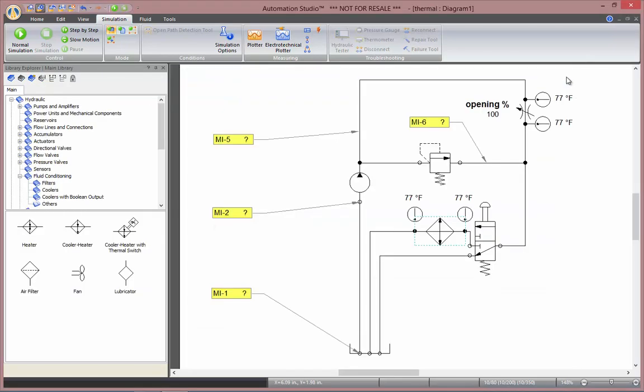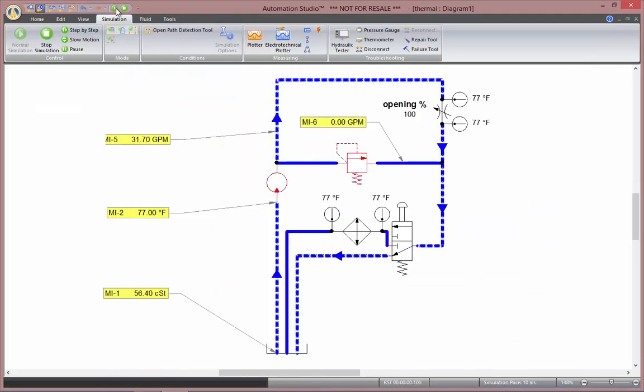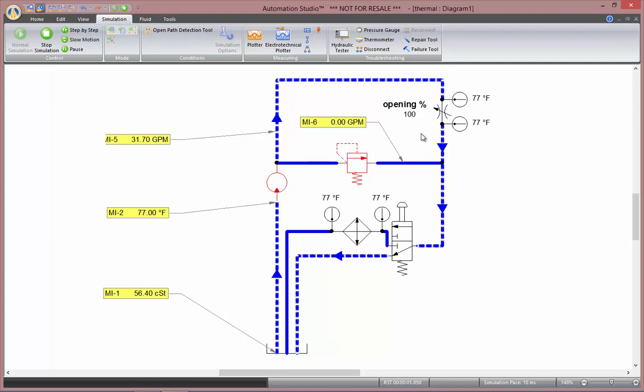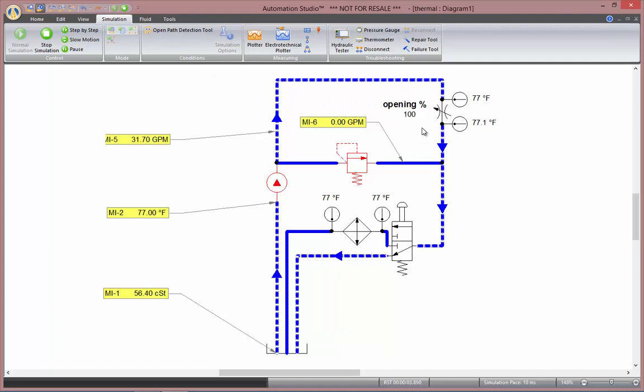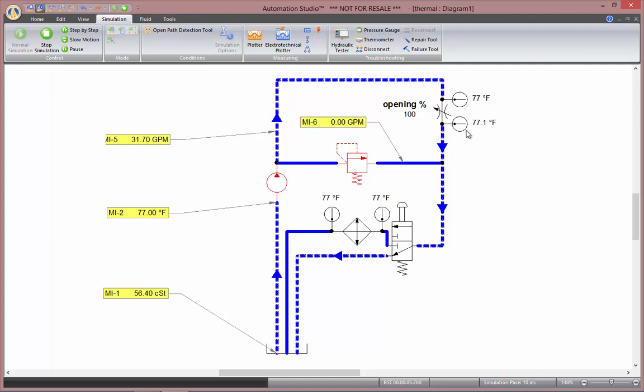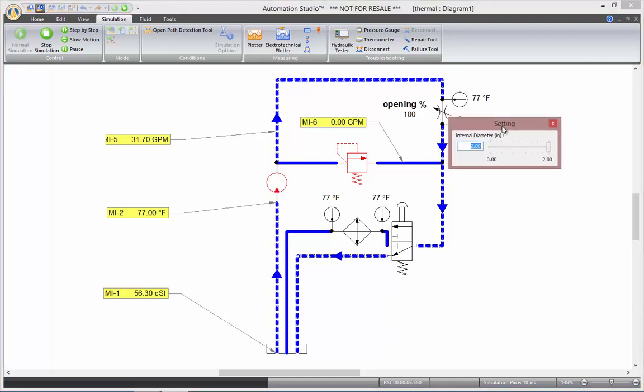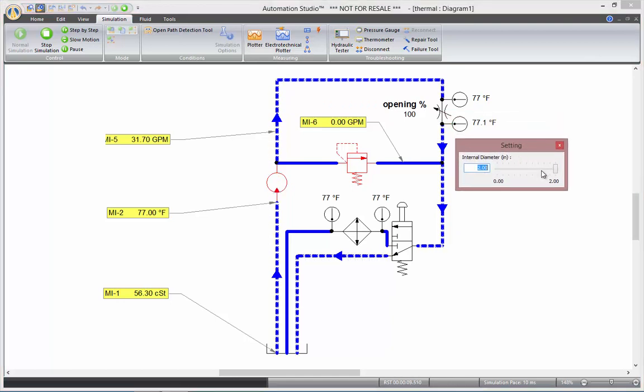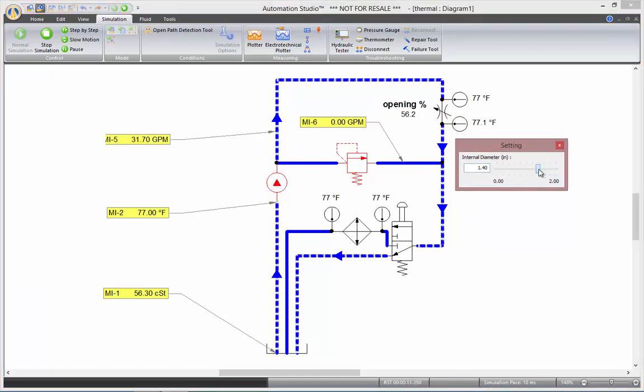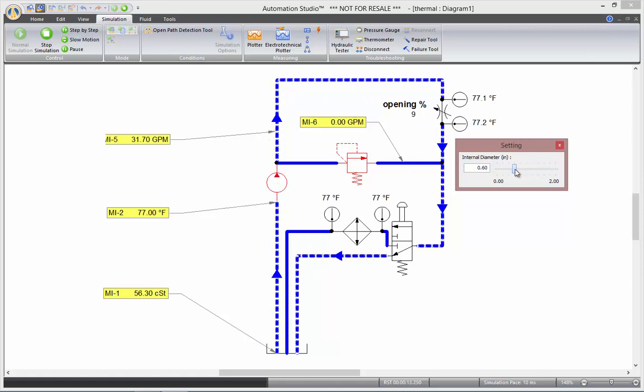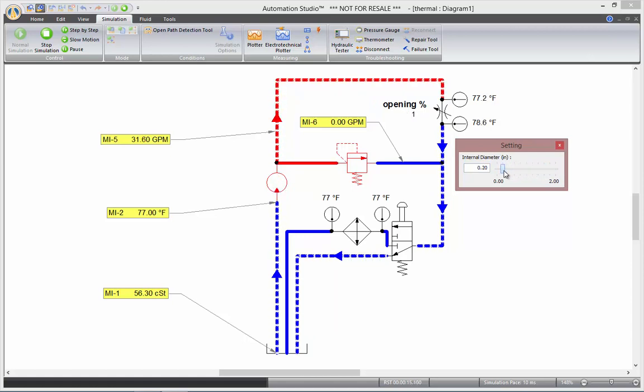Now we can go to Simulation. You'll notice here, with my opening at 100%, there's not much heat created in my throttle valve. But the more I close my orifice, the more turbulence is created, the more heat is generated, the faster the temperature goes up.